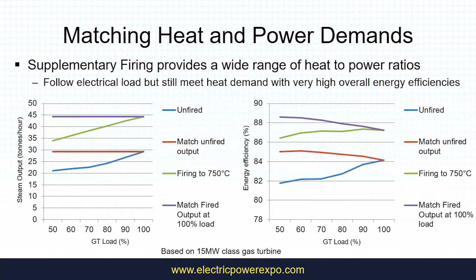Especially if you're a new build factory, they want that extra redundancy. And sometimes they'll replace their old oil-fired boilers with new gas-fired boilers at the same time. Now, one of the little tricks with the gas turbine is it doesn't use all the oxygen in the combustion process in the gas turbine, so the exhaust gases are oxygen-rich. So you can basically use an afterburner to boost your steam production, and that takes you from this blue line here, which is the variation of steam production with gas turbine load, up to this green line here, or if you want to, you can actually fire the boiler even more and keep constant steam production with variable electricity production.